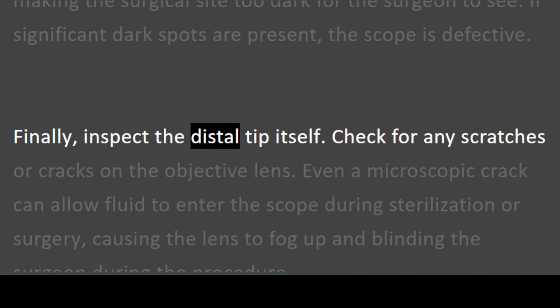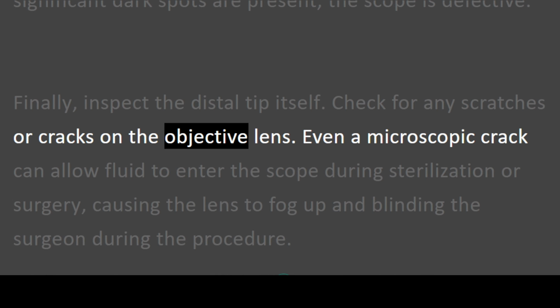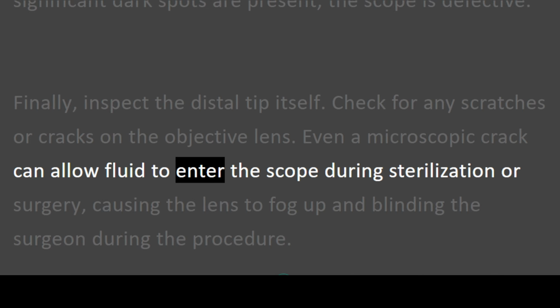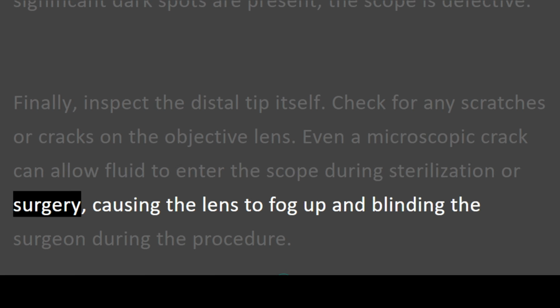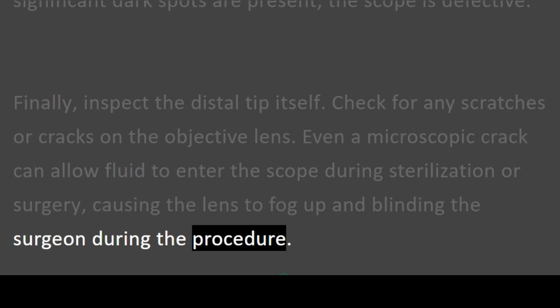Finally, inspect the distal tip itself. Check for any scratches or cracks on the objective lens. Even a microscopic crack can allow fluid to enter the scope during sterilization or surgery, causing the lens to fog up and blinding the surgeon during the procedure.